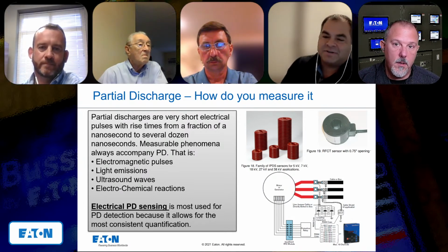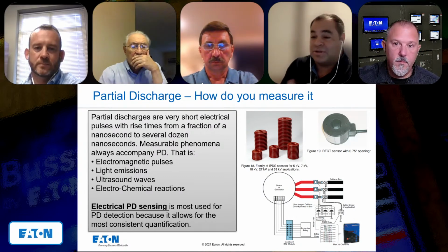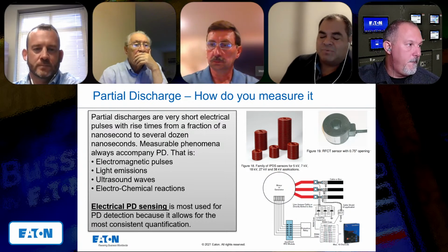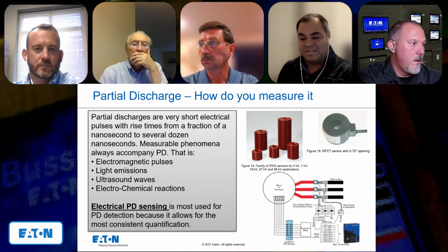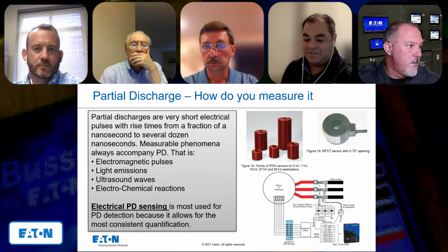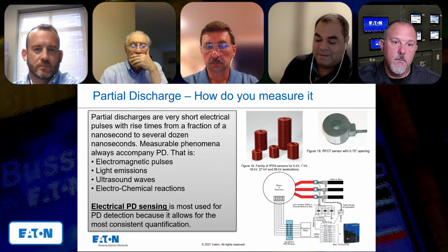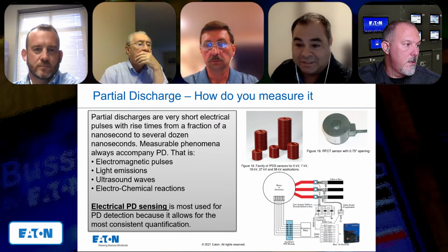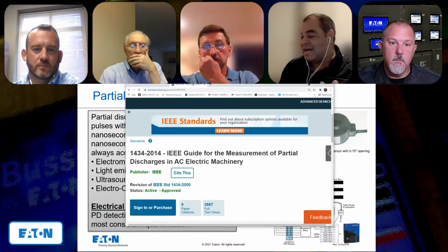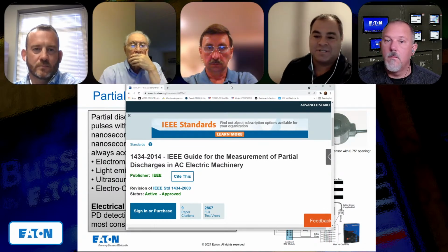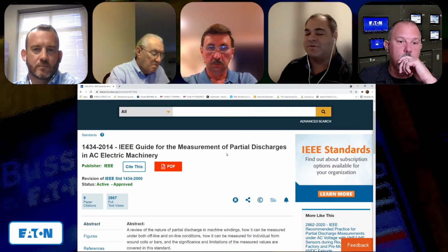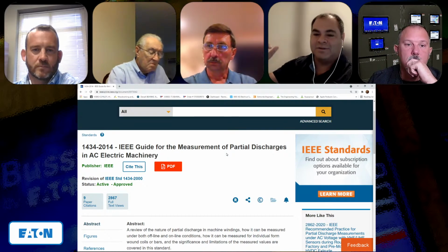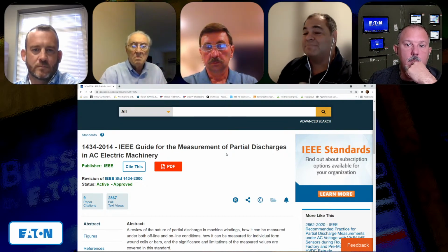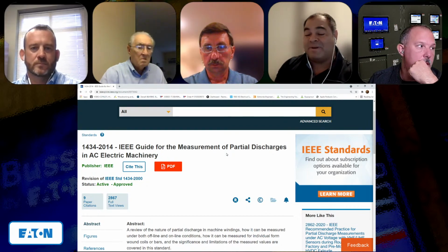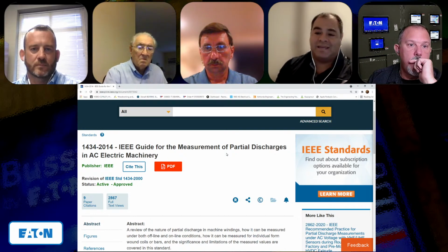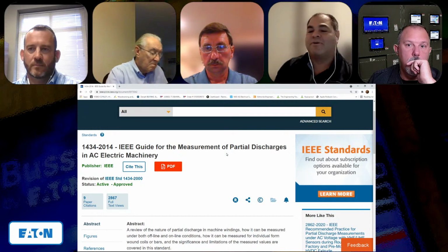We have an IEEE standard for partial discharge measurements, for example, in the laboratory during factory tests. And we have some recommendations on the equipment and the process to follow in the field. But what people are always looking for is the maximum value for the partial discharge. Outside of the laboratory, you don't have such a thing, because there are many factors: insulation type, equipment type, voltage levels, outdoor, indoors. So there is not a threshold where this is the maximum and you need to shut down. That's why it's important to follow the trend and do deeper analysis of the partial discharge. It's not only like an overcurrent relay, as you mentioned, that trips. It doesn't work that way.